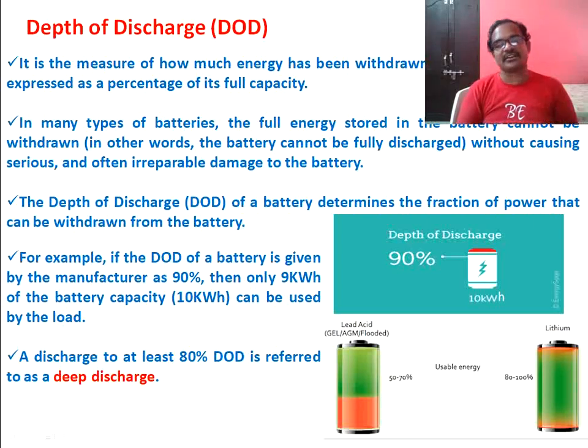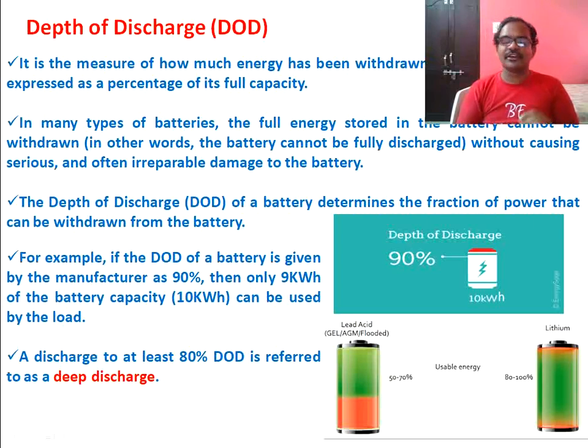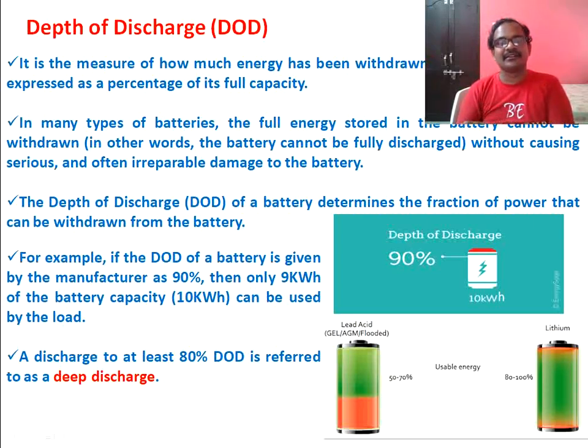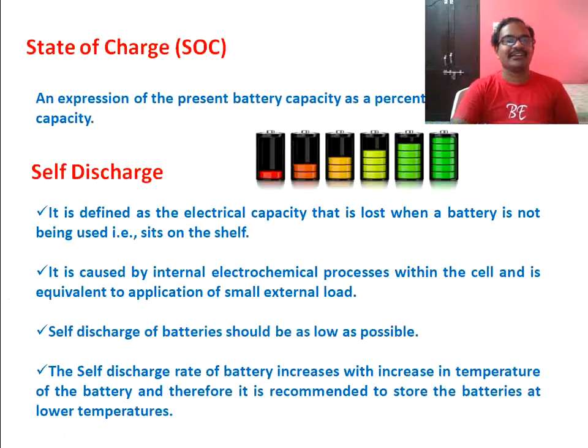For lead acid batteries used in PV systems, the depth of discharge is in the range of 50 to 70 percent. For lithium-ion batteries, the depth of discharge can be increased from 80 to 100 percent. The third parameter is state of charge (SOC) — the present battery capacity, i.e., the current state of a battery.